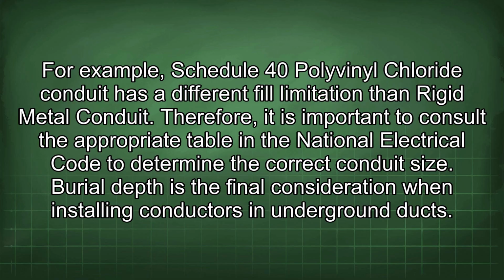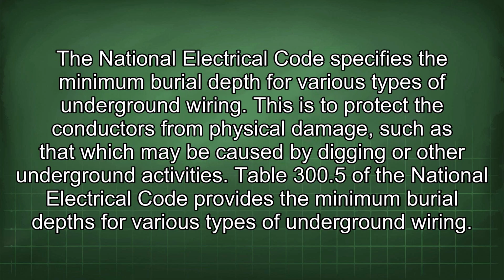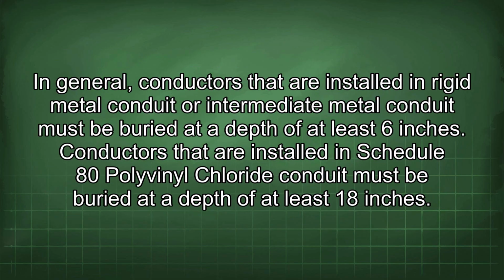Burial depth is the final consideration when installing conductors in underground ducts. The National Electrical Code specifies the minimum burial depth for various types of underground wiring. This is to protect the conductors from physical damage, such as that which may be caused by digging or other underground activities. Table 300.5 of the National Electrical Code provides the minimum burial depths for various types of underground wiring. In general, conductors that are installed in rigid metal conduit or intermediate metal conduit must be buried at a depth of at least 6 inches.